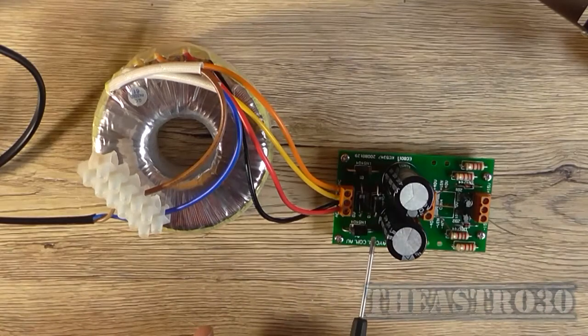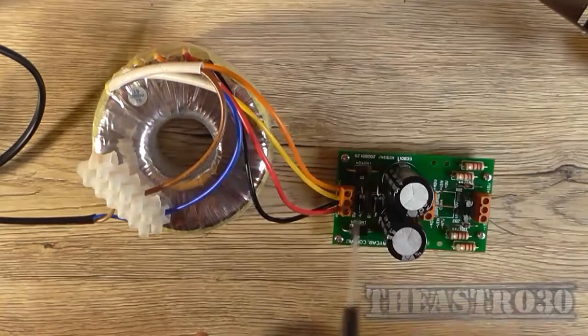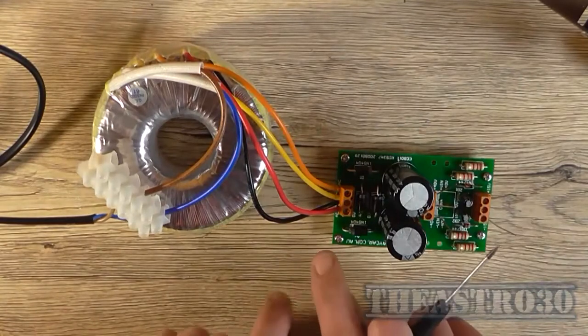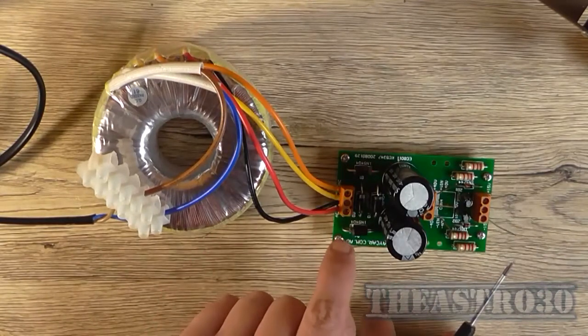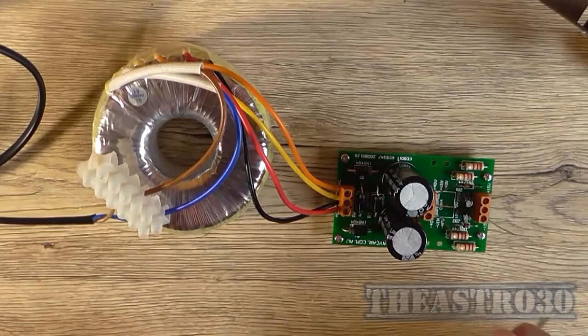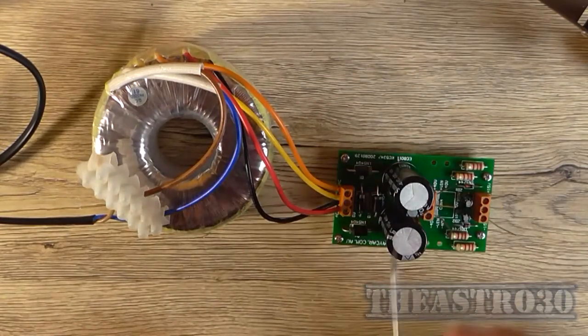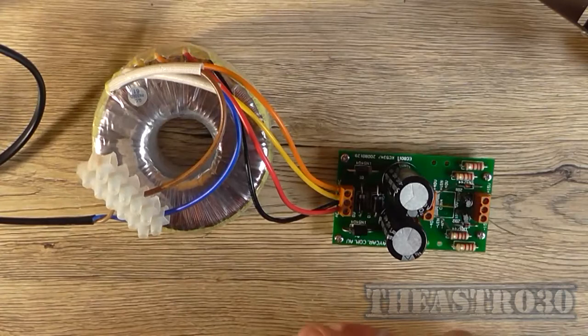It doesn't really matter for all intents and purposes which direction you wire the AC wiring, like if you put the red over here and the orange over here or vice versa. It doesn't really matter, as long as the secondary windings are in phase with each other. Put them out of phase and you'll either end up with half the voltage or no voltage at all. And if you wired them in parallel out of phase with each other, it would basically cancel itself out, so you'd have no voltage at all.